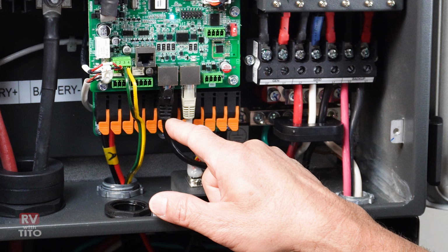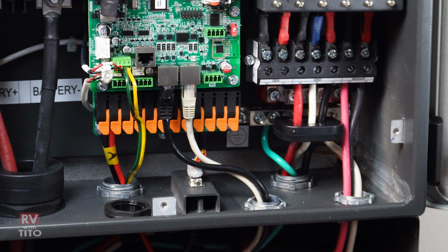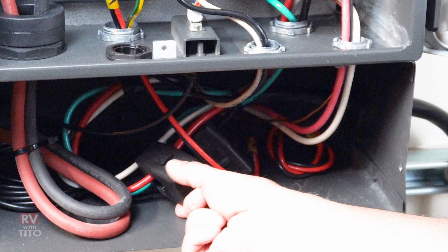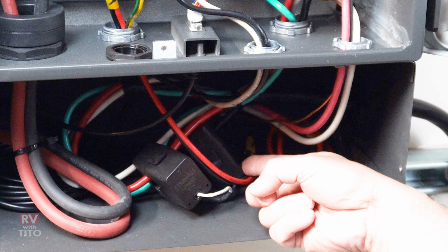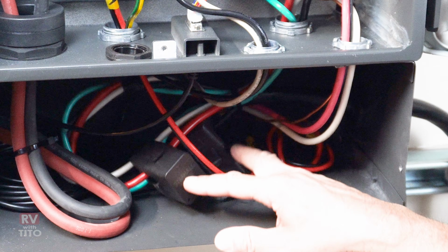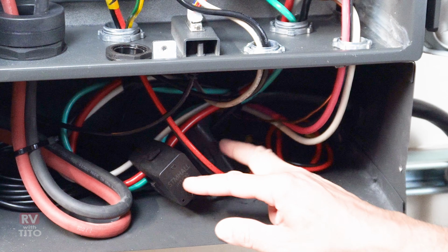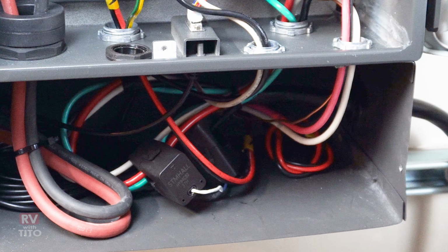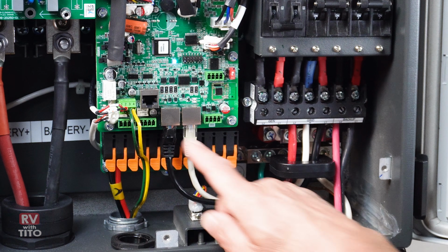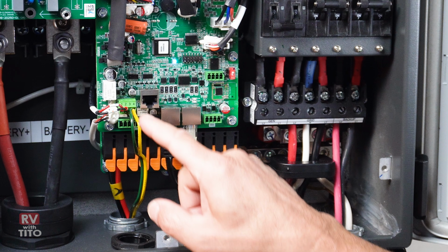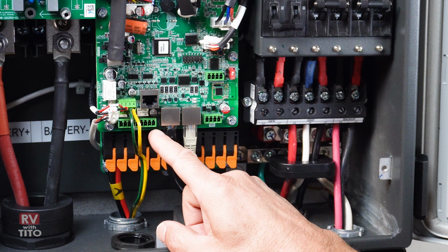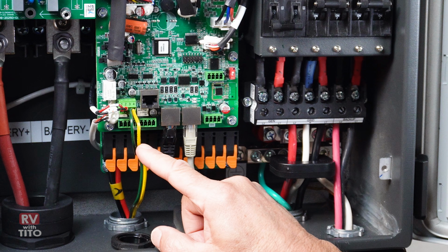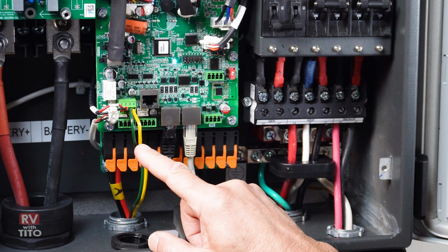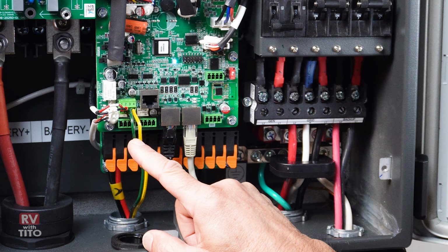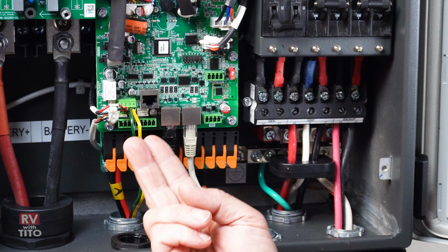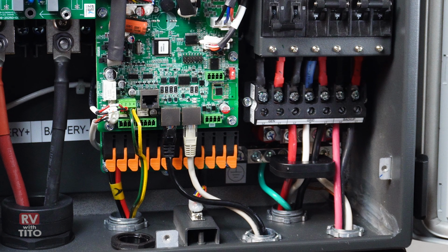This here is our CT, our current transformers. These transformers are measuring the current on L1 and L2 coming from the grid connection, I guess, and going to the grid connection. So those connect to here. Now on pins 3 and 4 on this plug is where I have my rapid shutdown switch connected, that's the yellow and green, and it basically connects those when I hit the switch, and it works pretty well.